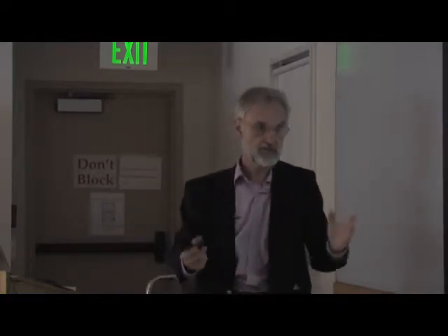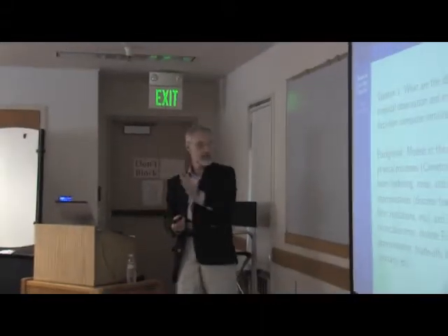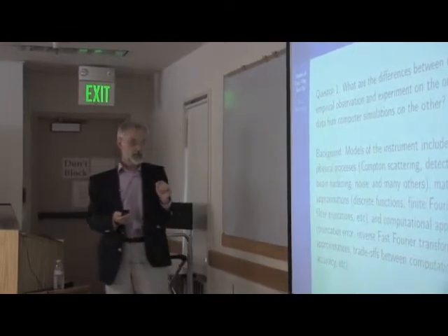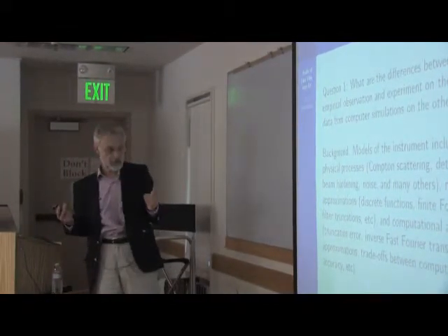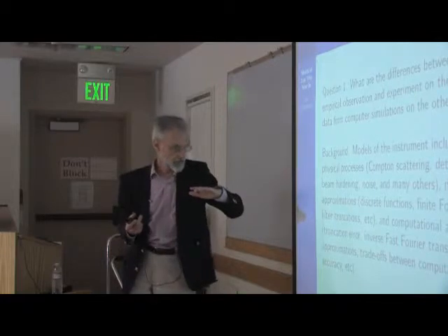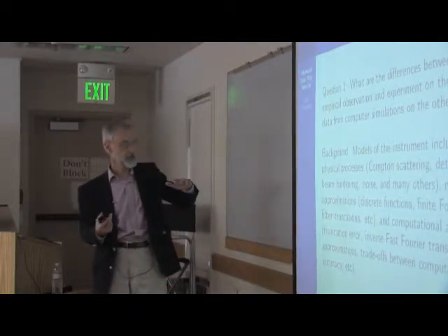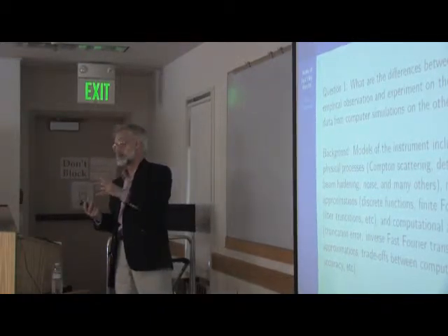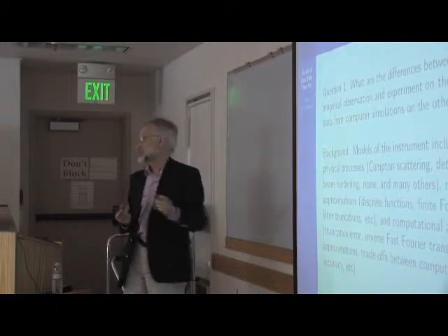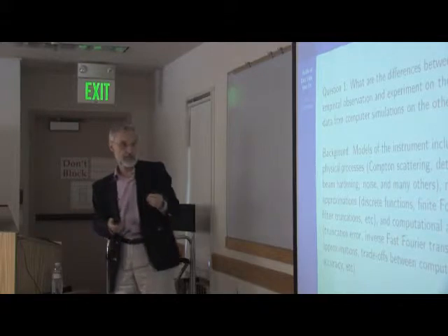Then there are mathematical approximations: you've got to go from continuous radon transforms to discrete versions of them, you've got finite rather than continuous Fourier transforms, filters get truncated after a point, and so forth. And then you've got familiar computational approximations — truncation error for real numbers, precision decisions to make, fast Fourier transform approximations. And there are very important trade-offs between the amount of computational time you're willing to devote and how much accuracy you want. There's a patient there; you've got to produce the image — that trade-off is crucially important.